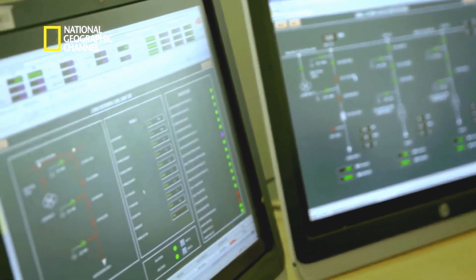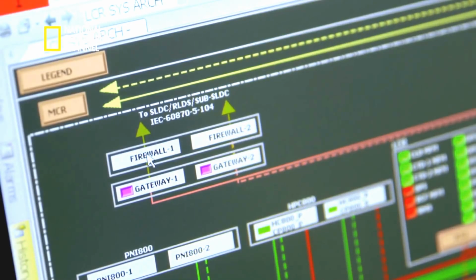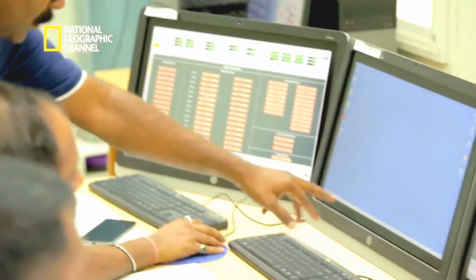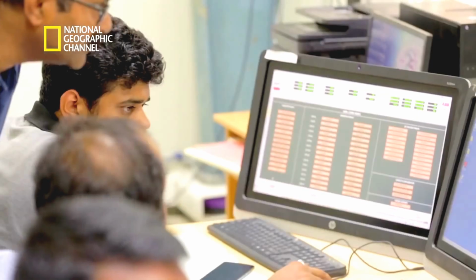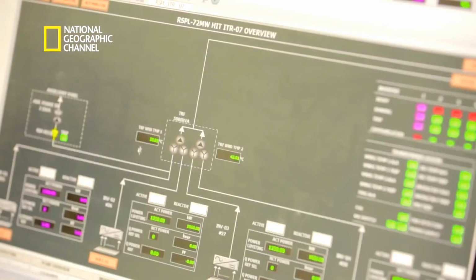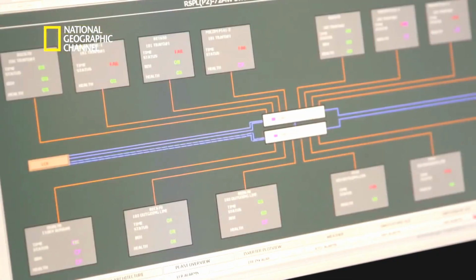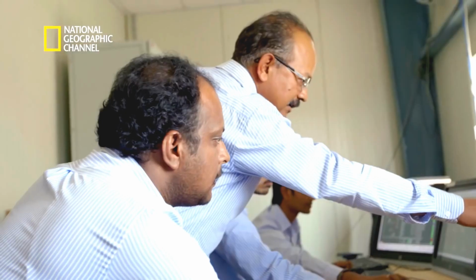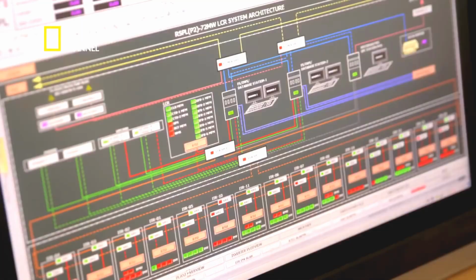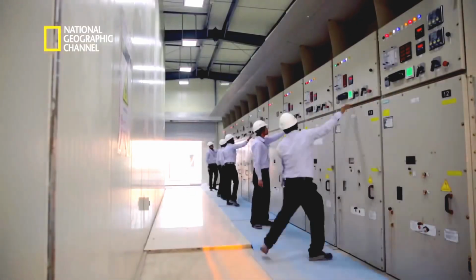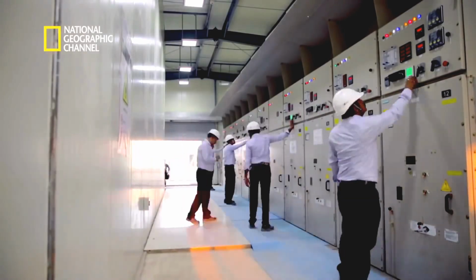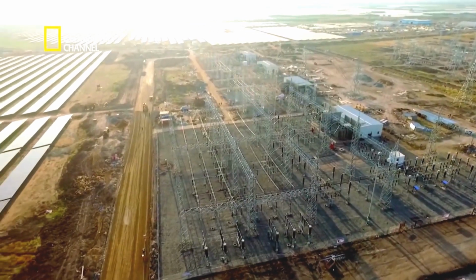This particular supervisory control and data acquisition system, or SCADA, was installed for a particular feature. Internally called the control philosophy, this feature allows limits to be set remotely on power generation, depending on the grid requirement on any given day, instead of field engineers being sent on site to turn down inverters according to the grid's demand.